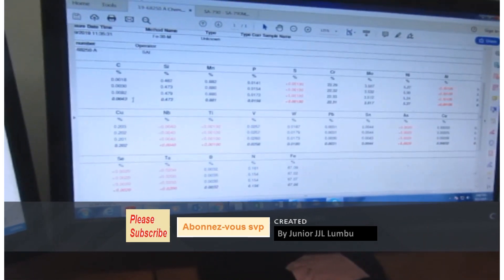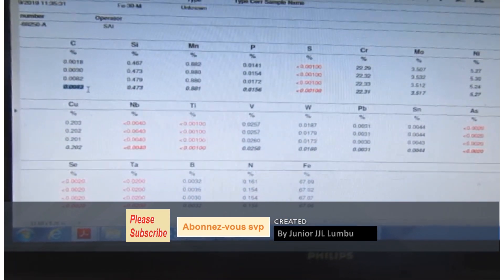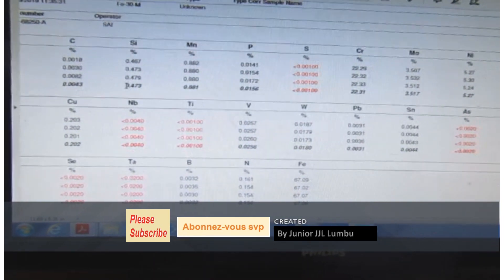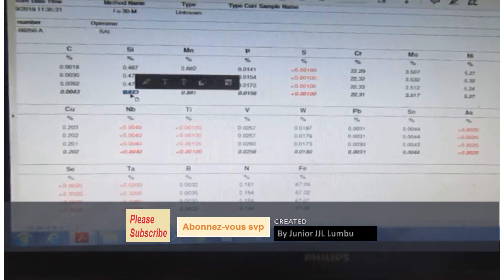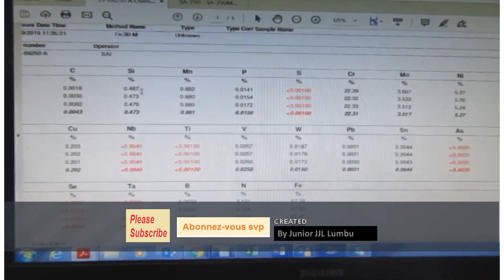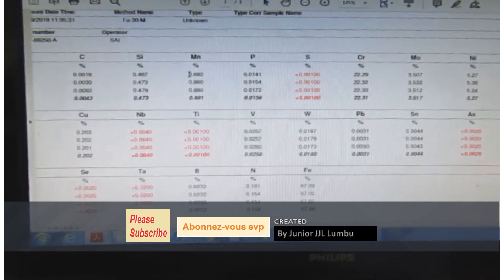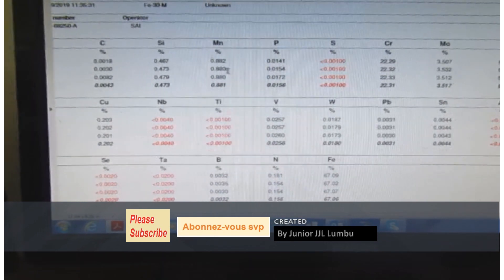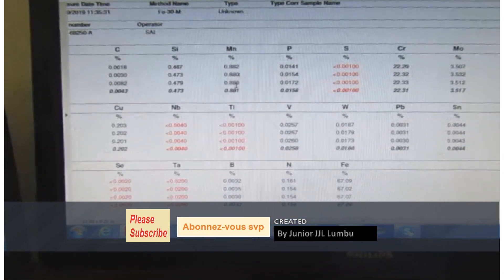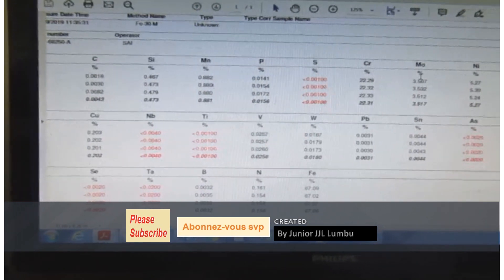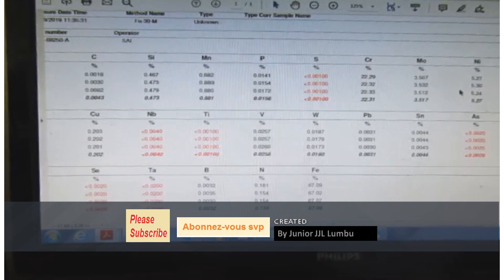This is a typical result of chemical analysis. After sparking, we got these results — this is the carbon content, this is the silicon content. The sample was sparked three times to get a consistent average. On manganese, the first reading was 0.882%, the second was 0.88%, and the third was 0.88% — very consistent. The same consistency applies to molybdenum, nickel, and other elements.